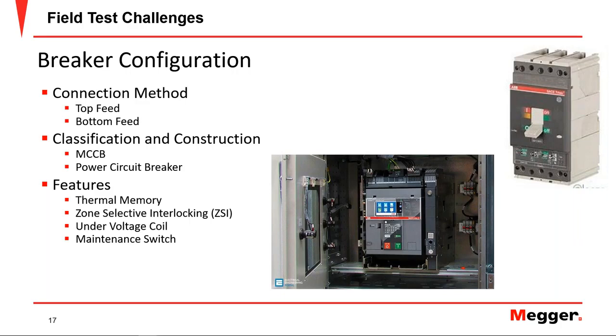If I have an under voltage coil, if that needs to be energized so I can test, and if there is any maintenance switch that has to be on or off during my testing, right? And the trip units as well, if I do need any external power, or the secondary injection tester. Again, those are typically provided by the manufacturer of the breaker. So I have to know what type of circuit breaker I will be dealing with when I go out in the field and perform these measurements.